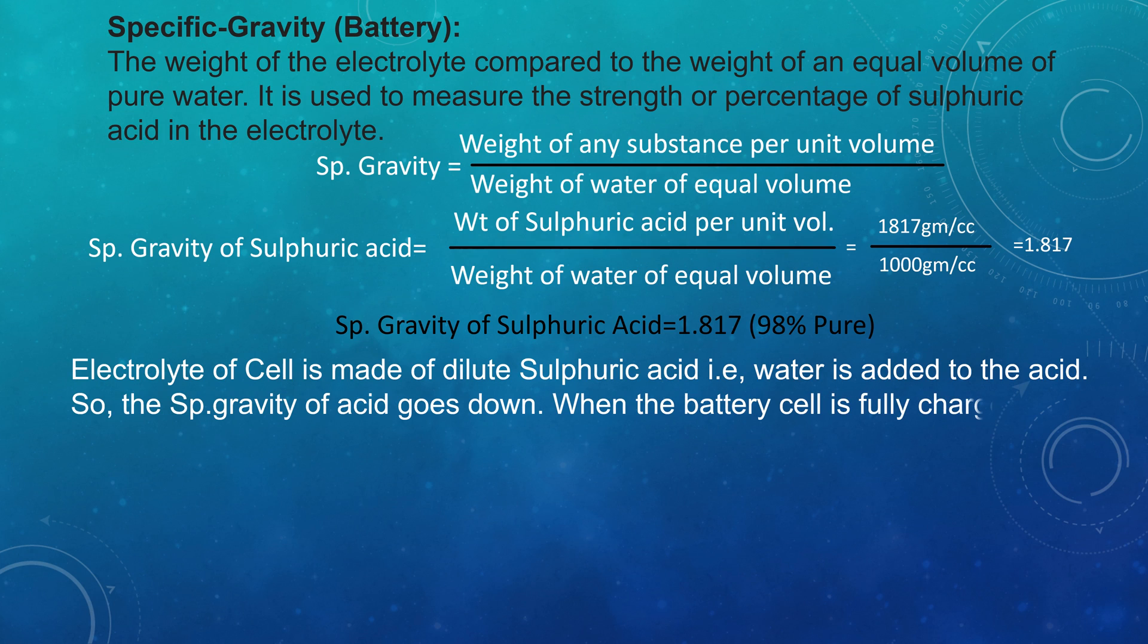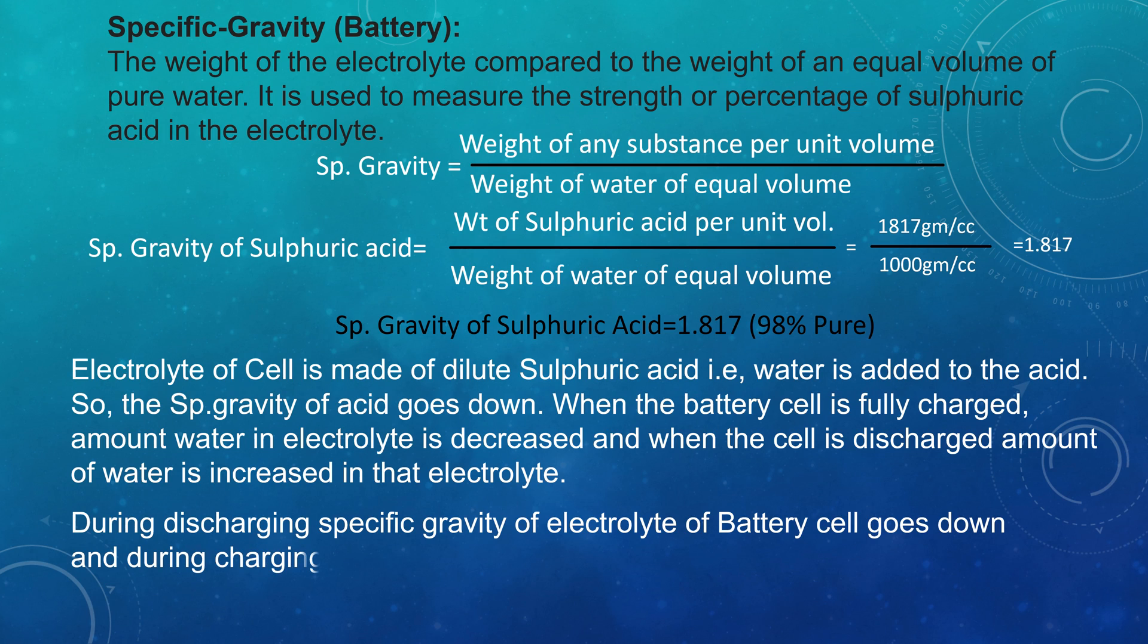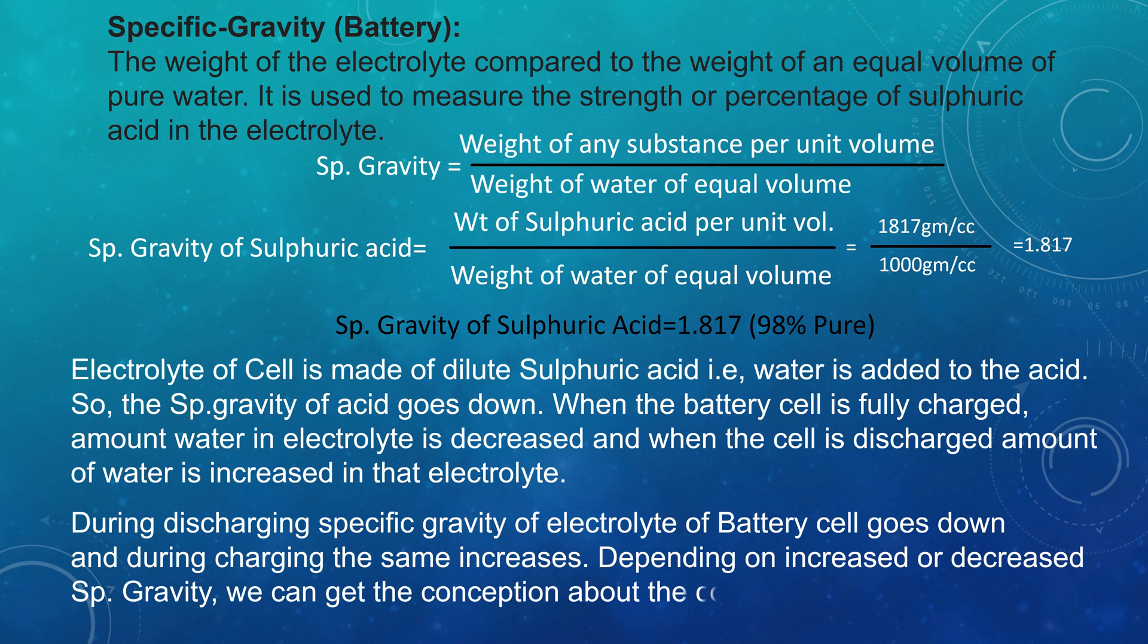When battery is fully charged, amount of water in electrolyte is decreased. And when the cell is discharged, amount of water increases in that electrolyte. During discharging, specific gravity of electrolyte of battery cell goes down. And during charging, the same increases. Depending on increased or decreased specific gravity, we can get the conception about the condition of the battery cell.